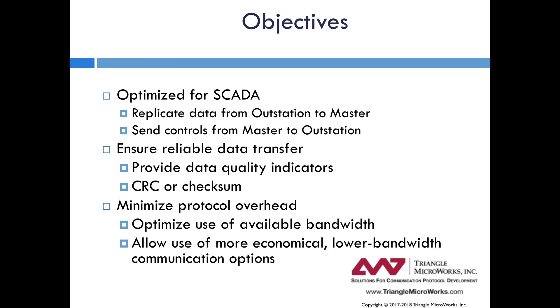In the standardization effort, there were a lot of objectives for SCADA. The main idea is to be able to send data from the outstation or the remote device to the master, and also to send controls from the master to the outstation, doing both of those in a very reliable way. The protocol includes some quality bits and a CRC and checksum to make sure the data and the messages are correct. Another goal was to make sure that bandwidth was optimized, so it's not sending a lot of unnecessary messages. Remember, in the early 90s bandwidth was pretty expensive, so unlike today where we take gigabit ethernet for granted, when dealing with dial-up lines or slower, minimizing protocol overhead is a big concern.